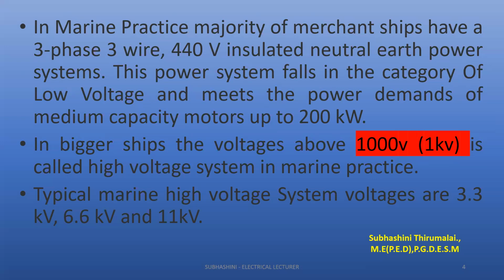Typical marine high voltage system voltages are 3.3 kV, 6.6 kV, and 11 kV. These are used in container ships, some LNG gas carriers, cruise liners, and fuel and oil production ships. This type of ship requires more voltage, so it comes under the HV system: 3.3 kV, 6.6 kV, and 11 kV. These are the typical marine HV system voltages we have.